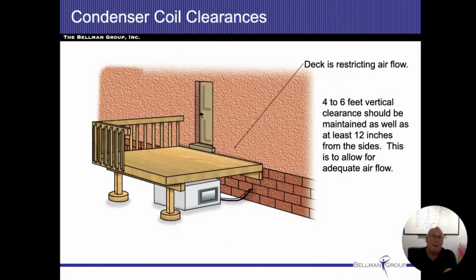I see this every now and then. Somebody will put an air conditioning coil under a deck. And again, it's only really a problem if you think that the airflow is being limited. You know, for a rule of thumb, they tell us 4 to 6 feet vertical clearance. I don't know if I could buy into that 100%. I think it would work just fine. But when you're talking about only 6 inches to a foot, yeah, that could probably restrict the airflow.